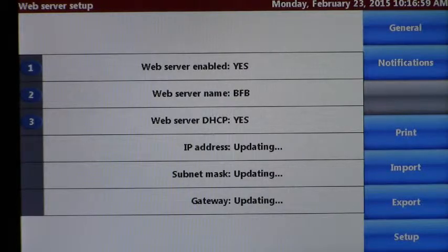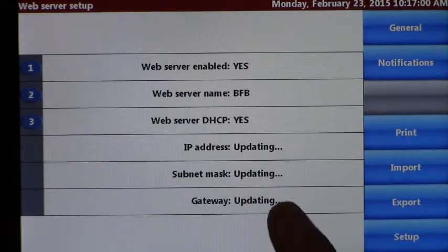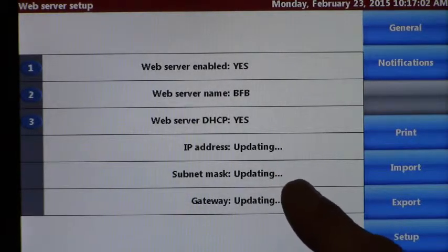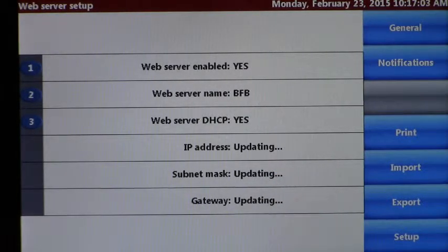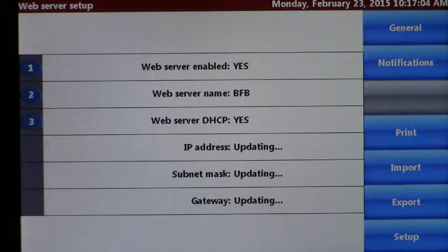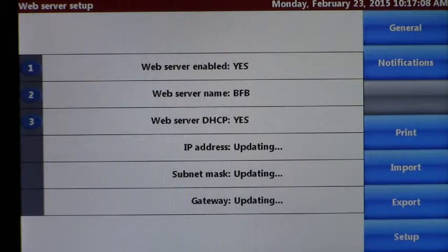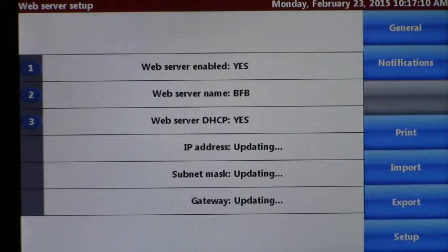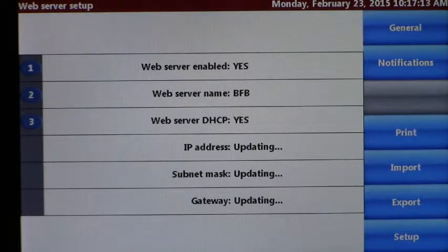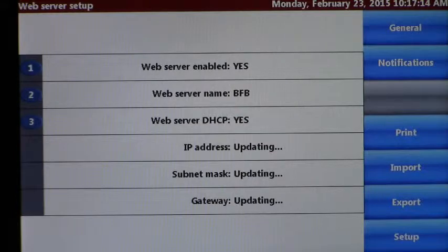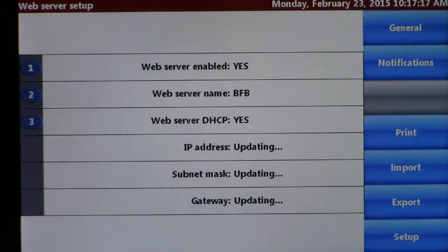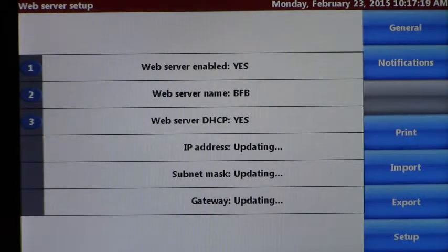If you'll notice it says updating, which means it's automatically going out to the network and waiting for an IP address to be automatically assigned. I do not have my instrument connected to the network and that's why it continues to say that. If you don't have an active network it'll continue to say that forever.